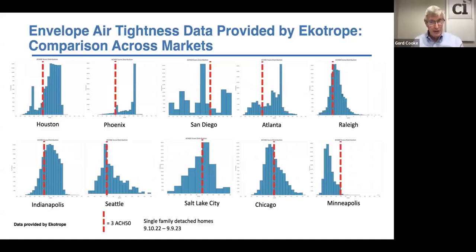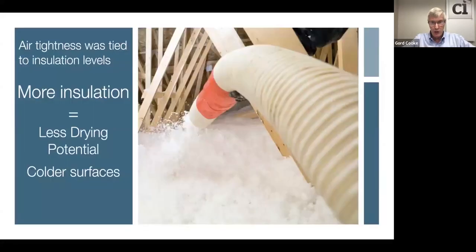So this was thousands of houses, different climate zones between fall of 2022 and fall of 2023, a snapshot of houses. Notice down at the bottom right, Minneapolis seems to have figured this out. And frankly, you would say, I wonder why they figured it out. Well, that was the first place in the country, way back in the 70s and 80s, to increase insulation levels. And we'll chat about the link between increased insulation levels and air tightness. They came about it organically and have found systems and methods. They would say they can meet 1.5 air changes per hour. They can certainly meet the 3 air changes per hour pretty quickly, but clearly other places haven't quite figured out where we need to get to.